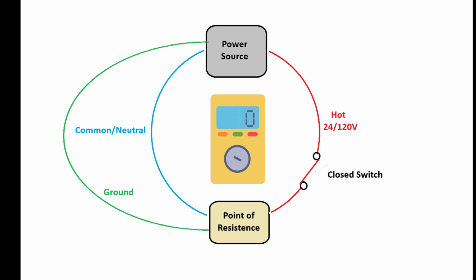So what I would do is I would put my probe on the hot side of that switch. I would take my other probe and select a reference point close to the power source at the common terminal of a transformer, for example, and I should be reading 24 volts there on that hot wire.